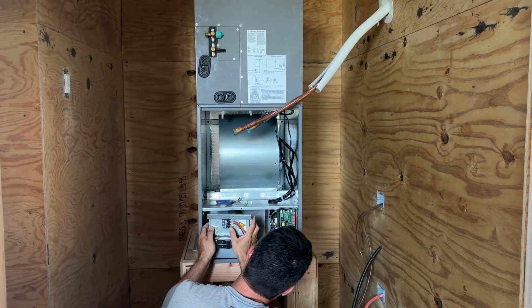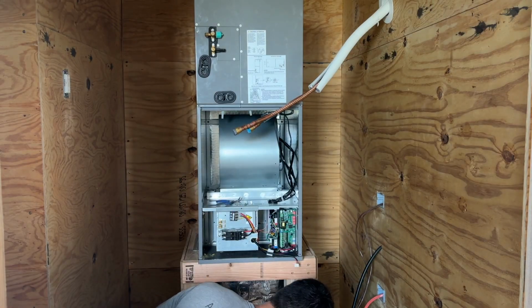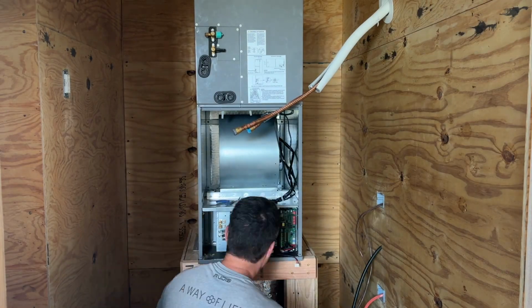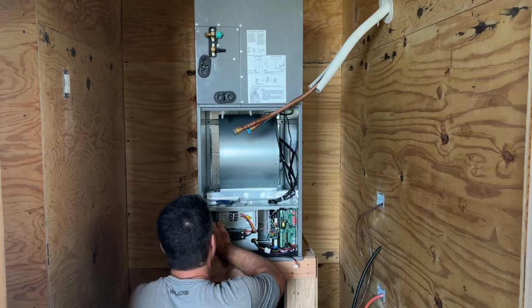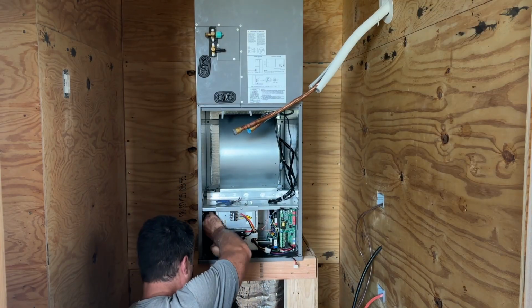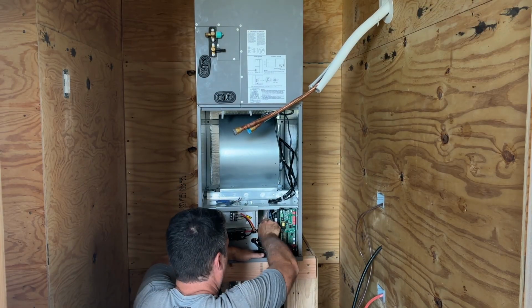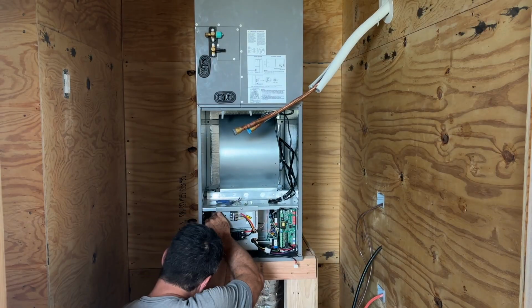We're going to go ahead and put this auxiliary heat module back in. I had to take it out to mount the unit on top of the stand. I was running screws through the side of the sheet metal on the unit, and I wanted to make sure there wasn't anything on the back side that I was going to hit. So we took that module back out.